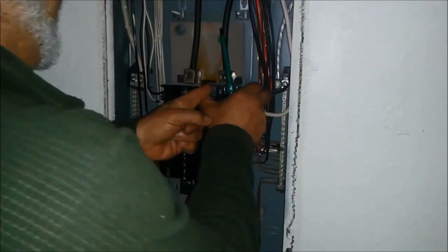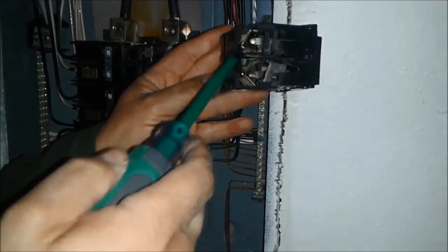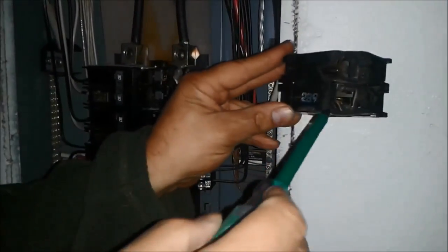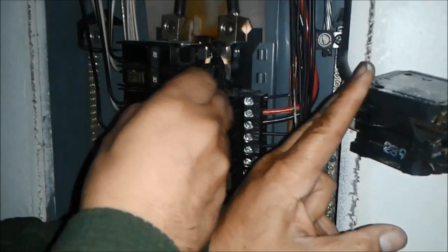I am going to work with gloves, and now I have to remove this breaker and I am going to use a screwdriver for that. You can see it is removed. That is the wire — if you look very carefully you can see it is already burned here. You can see it is burning, dead, it is gone. This one, if you can see, it is already burned and that is broke. You can see inside what is going on — everything is really burned.